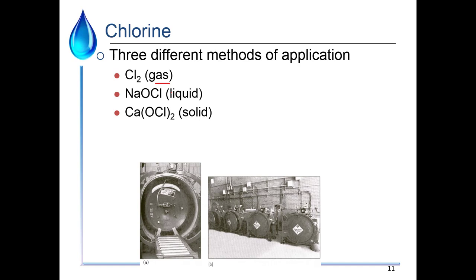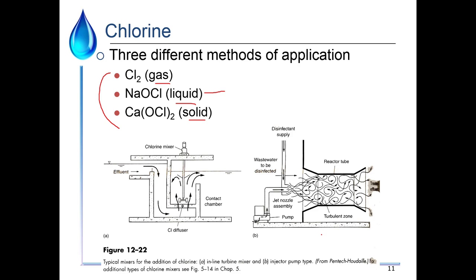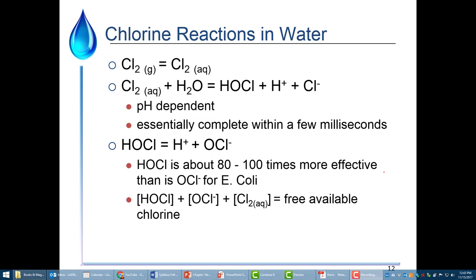We can apply disinfectants in three different ways: gases, liquids, and solids. For chlorine specifically: chlorine gas is the gaseous form, sodium hypochlorite is the liquid form — essentially bleach — and calcium hypochlorite is the solid, similar to pool tablets. Here are some old pictures of gaseous chlorine tanks, and we can see the chlorine mixers for applying these to the water itself.